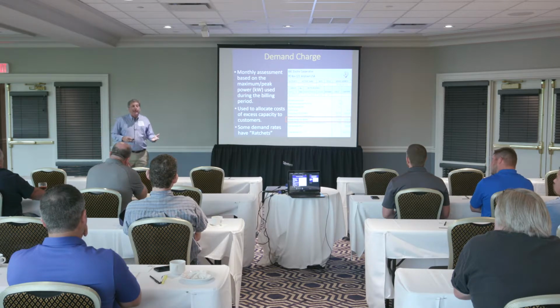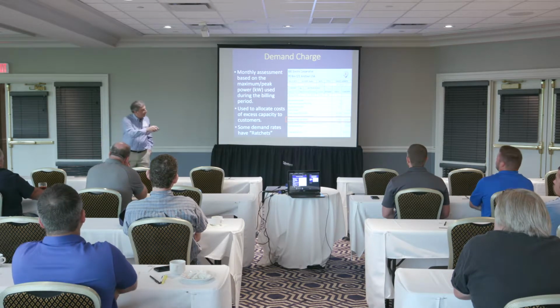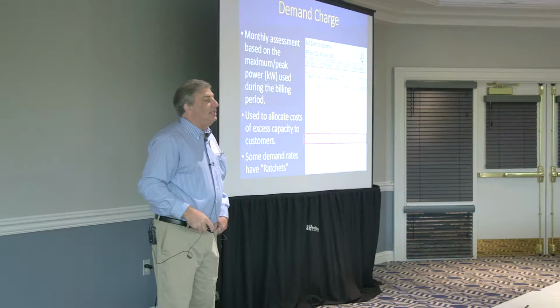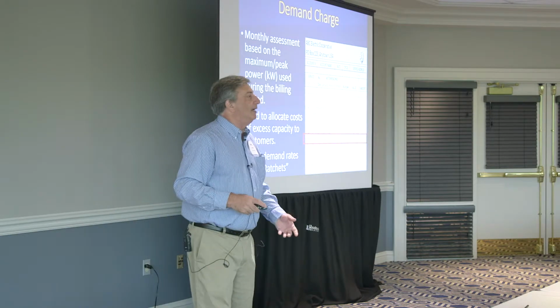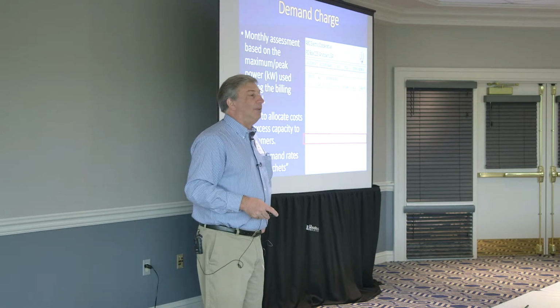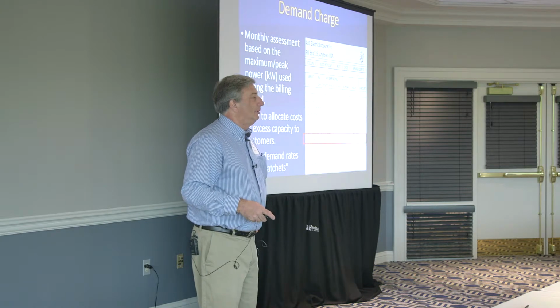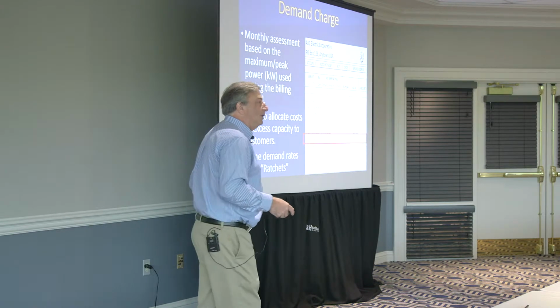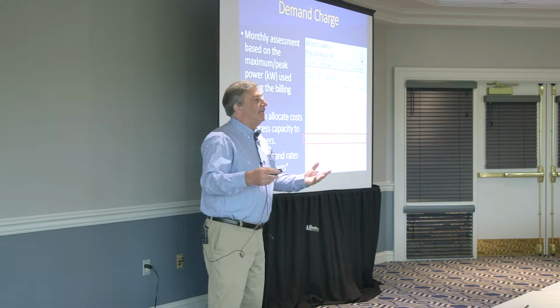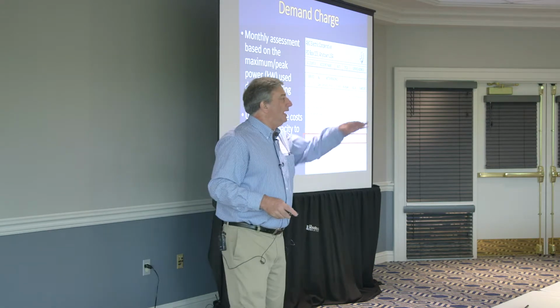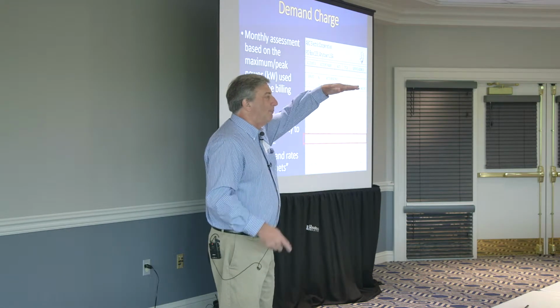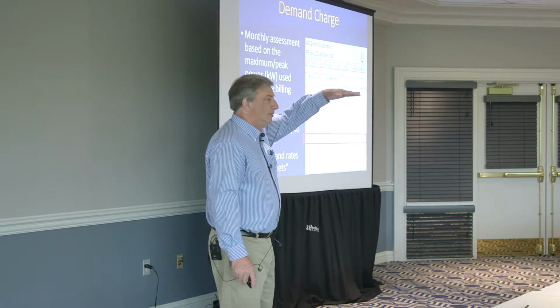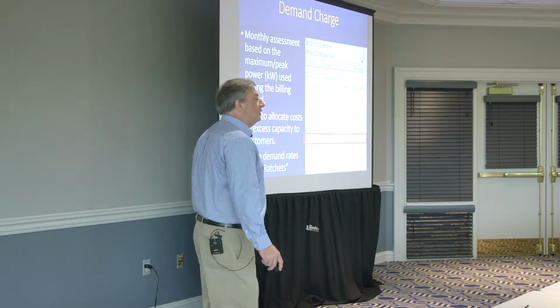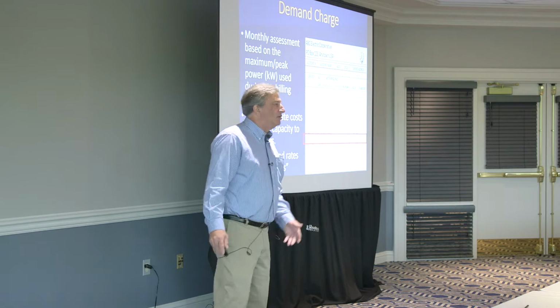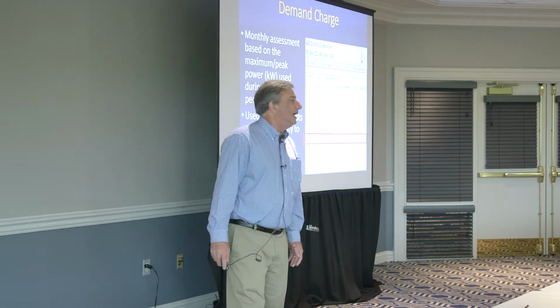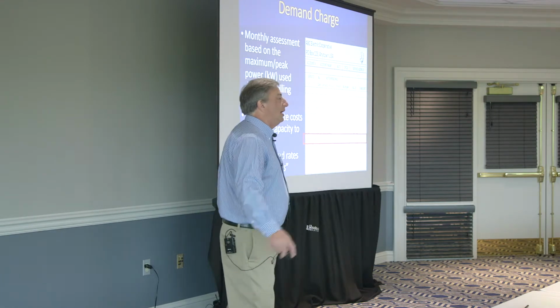Typically in the old days, when they got to 80% of that number, the energy management system sent a signal to the physical plant's pagers. That signal meant this is a stage 1 demand warning, we're at 80% of the maximum we want to ever pay. So they start looking around and saying, are there things we can shut off that we don't need right now, things people have left on?